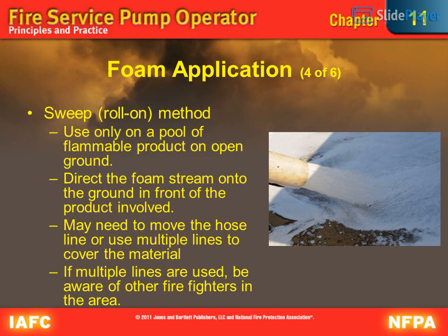Foam application, 4 of 6. Sweep, roll-on method. Use only on a pool of flammable product on open ground. Direct the foam stream onto the ground in front of the product involved. May need to move the hose line or use multiple lines to cover the material. If multiple lines are used, be aware of other firefighters in the area.